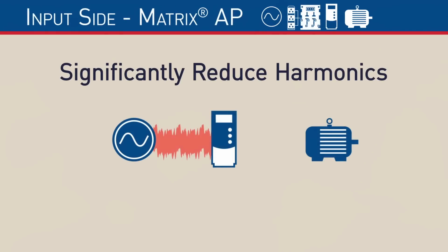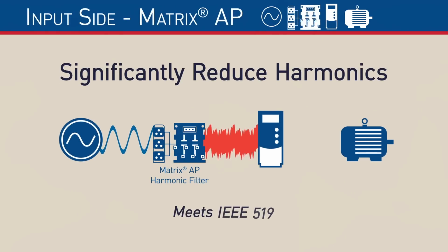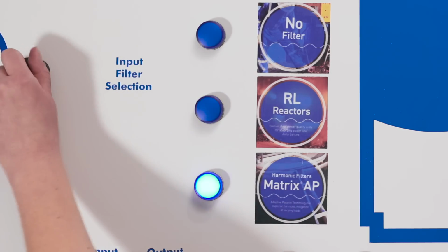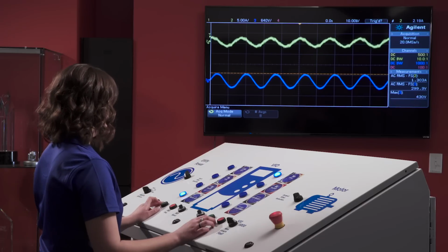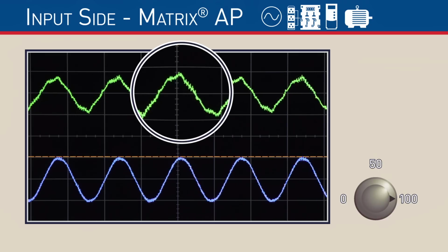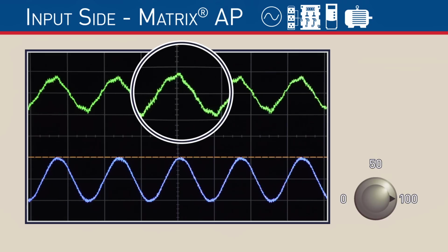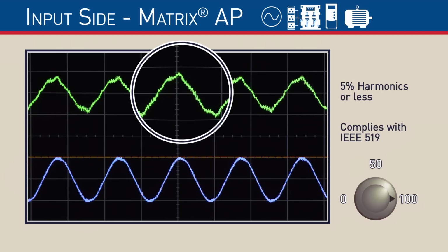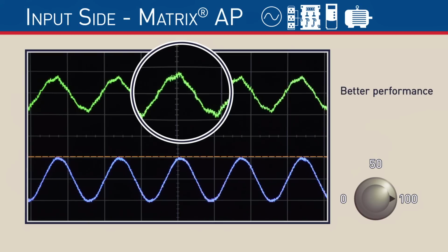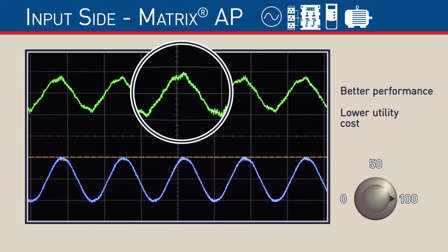But if we want to significantly reduce harmonics or meet IEEE Standard 519, we can introduce a Matrix AP harmonic filter. Let's start the Matrix AP with everything running at 100% load. We can see that the current waveform is relatively sinusoidal, representing a significant improvement to our power quality. The harmonics would now be at 5% or less, which will comply with the IEEE Standard 519. With the Matrix AP, the overall system will experience better performance without the risk of utility penalties.